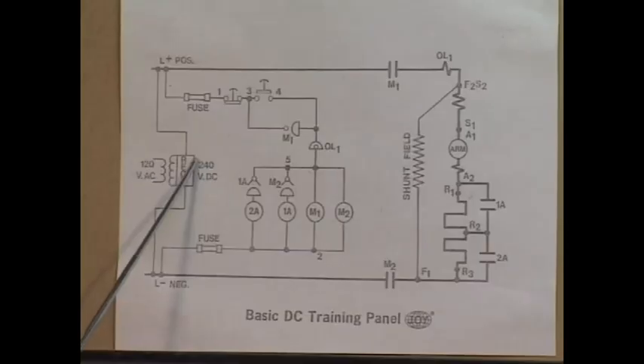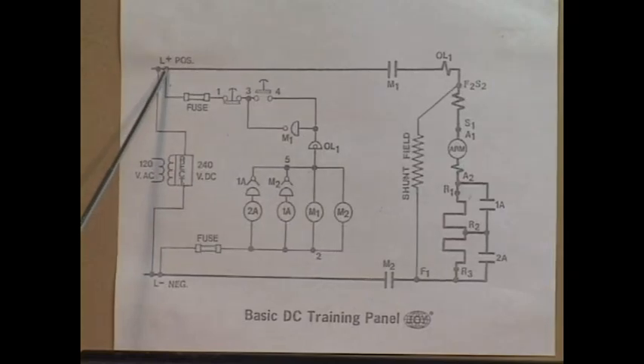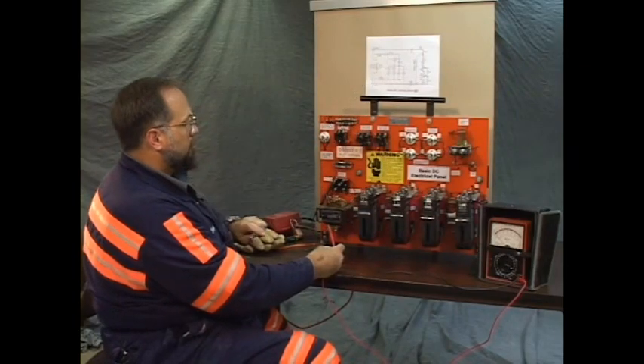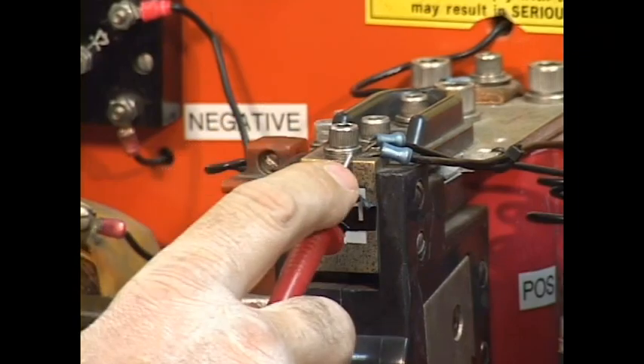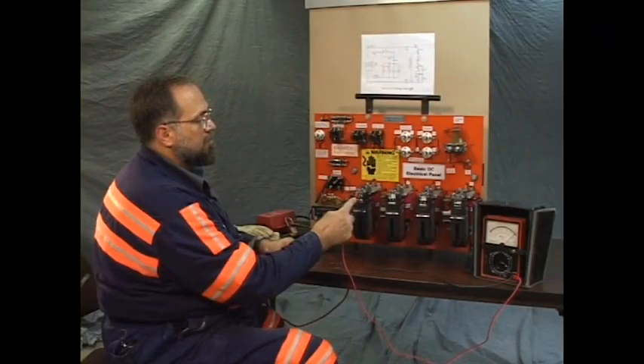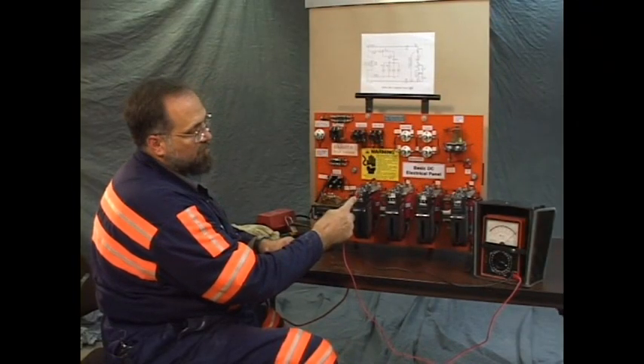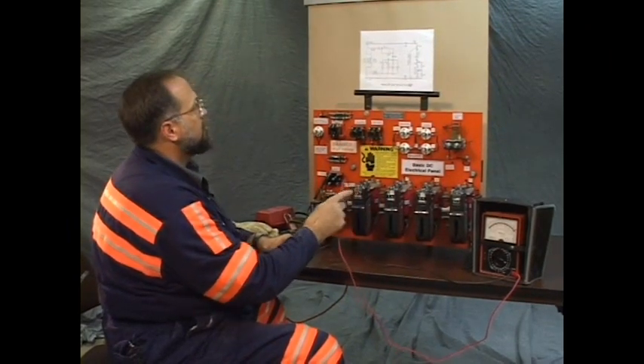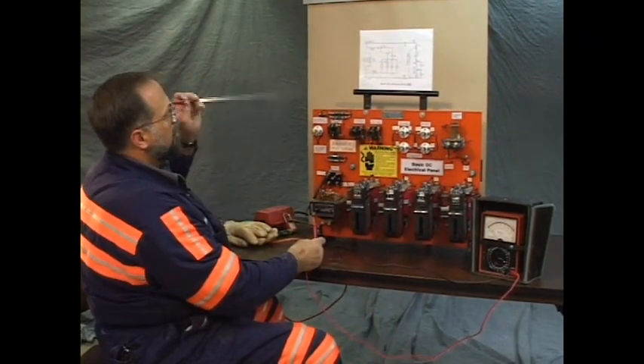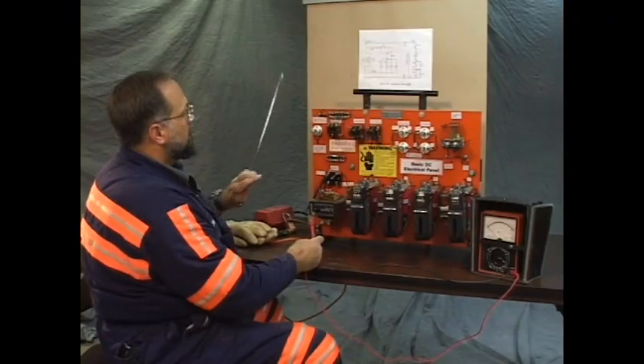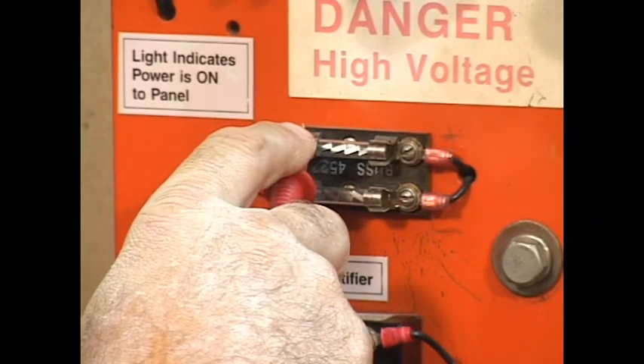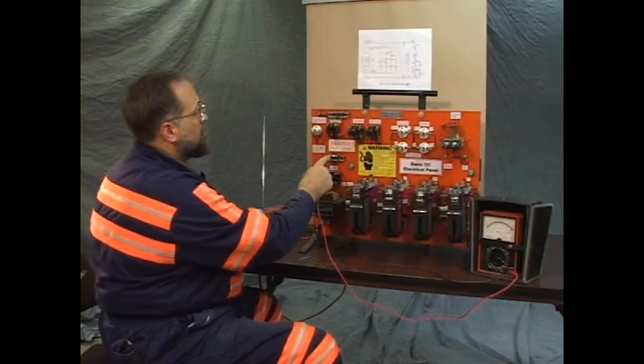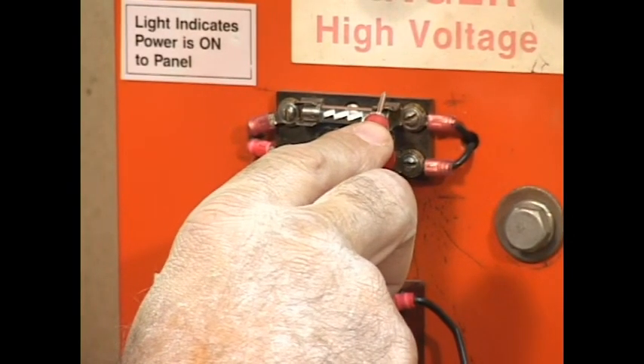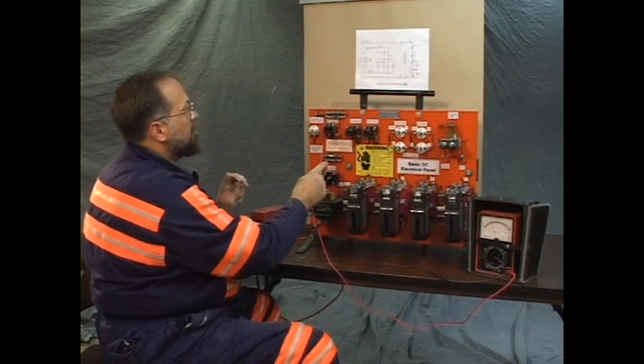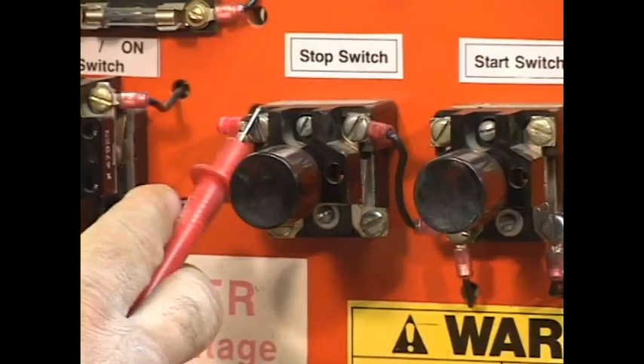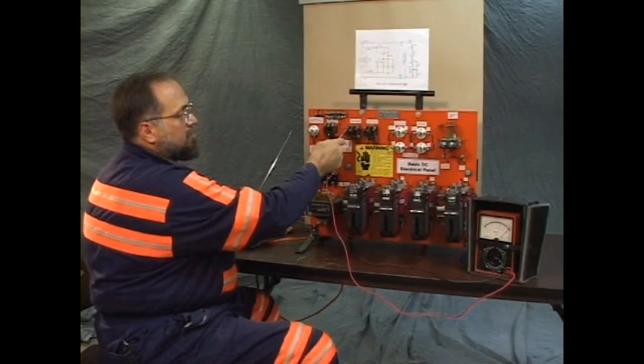First point from the positive of the rectifier, it shows to the L positive point on the drawing, which is the top front of the M1 starter. And as you can see by the meter, we have continuity. It's good. The next point, as you see on the print, is the line side of the positive fuse, and it's good. I'm going to proceed to the load side of the positive fuse, and it's good. And I'm going to go to the line side of the start switch, which is good.